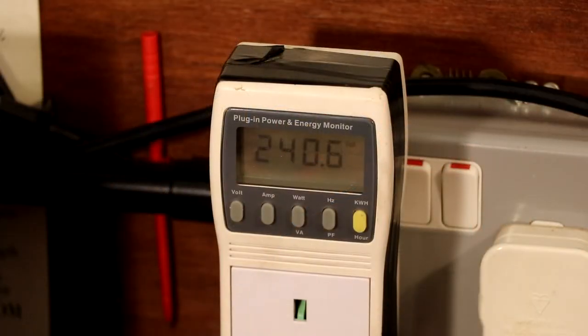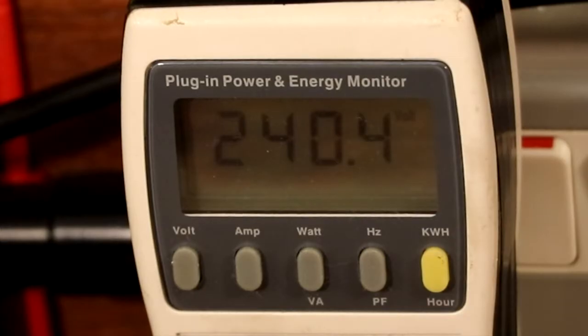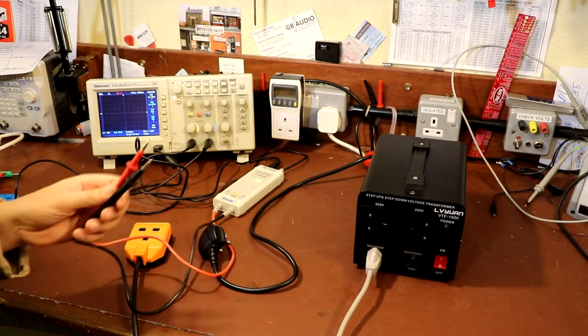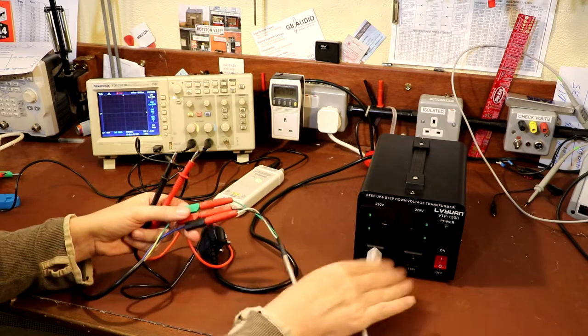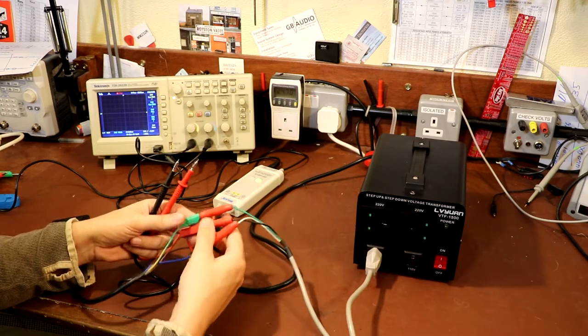So you can see that the mains voltage coming out of our socket here is 241 volts. Nominally in the UK it should be 230 now, but because I've probably got quite an old supply transformer, it gives around 240, and it's not untypical for my voltage here to be 251 or 253. It tends to be quite high here, so a voltage of 240 is pretty low for me. So you can see that my domestic supply is around 241 volts at the moment. Now I'm going to connect up the differential probe to the output from our step down transformer.